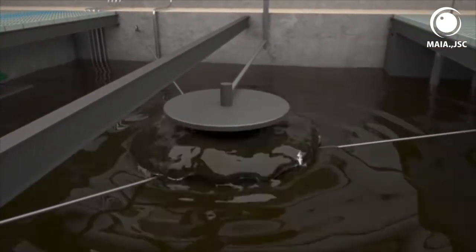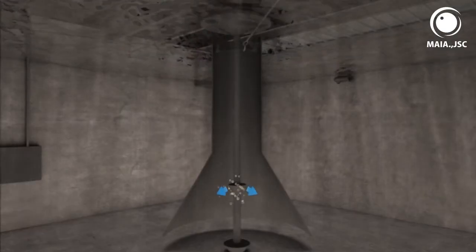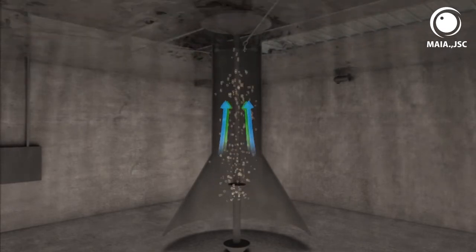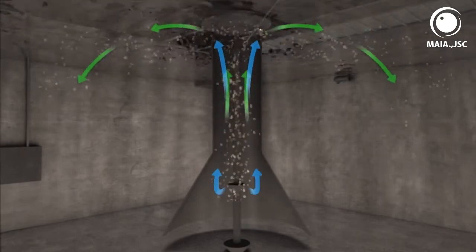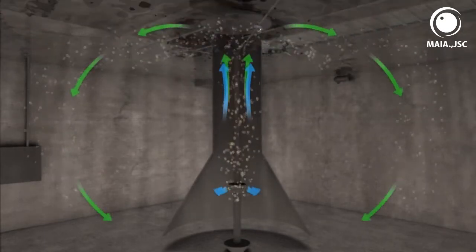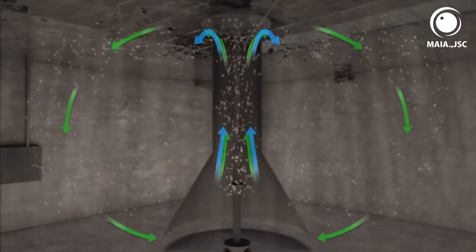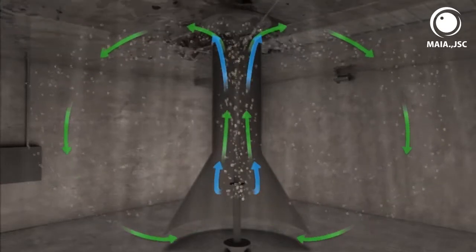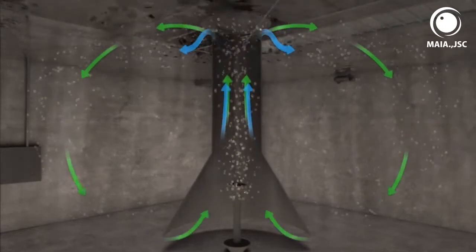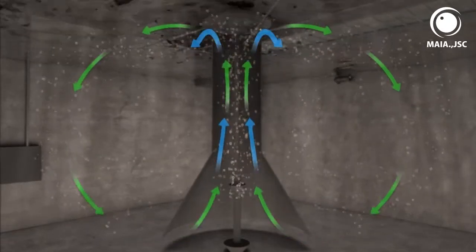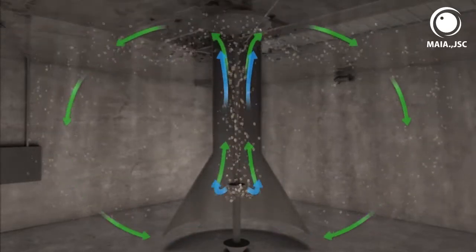The aeration chamber is where 90% of the actual wastewater treatment takes place. In the middle of the tank is a large pipe with a flare at the base. There is an opening at both ends and a splash disc at the top. An air supply pipe runs down the center and continually releases air into the lower section of the pipe. As the air mixes with the wastewater, it naturally rises up and deflects outwards off the splash disc. This upward flow draws in more wastewater from the opening at the bottom and creates a gentle circular mixing motion throughout the entire length of the chamber.